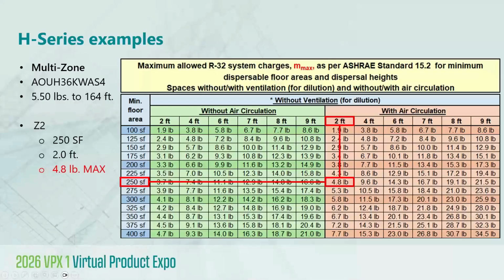So thinking this through, what options could you propose in order to make sure the dispersal volume could manage that entire 5.5 pounds? Well, the first and perhaps simplest solution would be to consider a different indoor unit that provides an increase in the dispersal height, such as a wall-mounted indoor unit. That is, of course, if the option is acceptable to the homeowner. But using a 7-foot dispersal height, in that column you see that in the green cells, even without air circulation, the maximum allowable charge is 12.9 pounds.